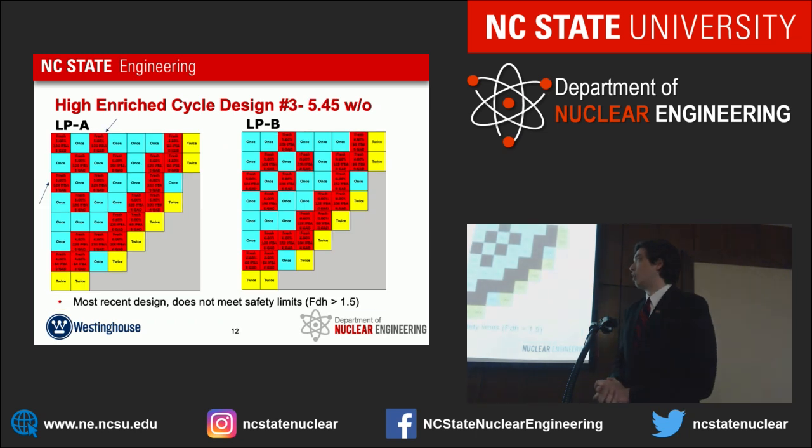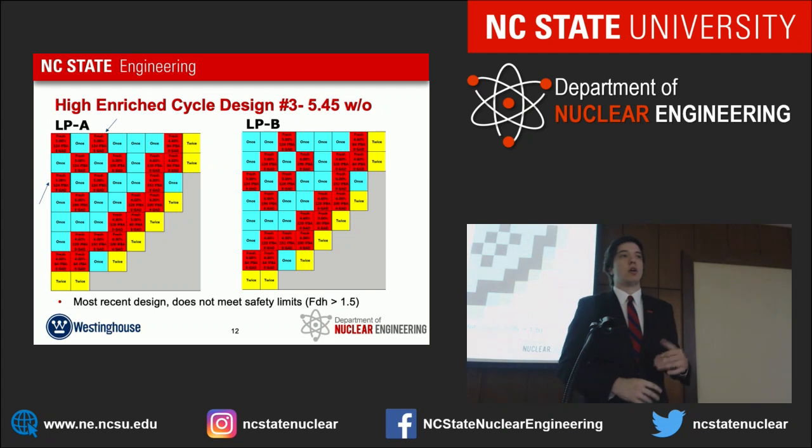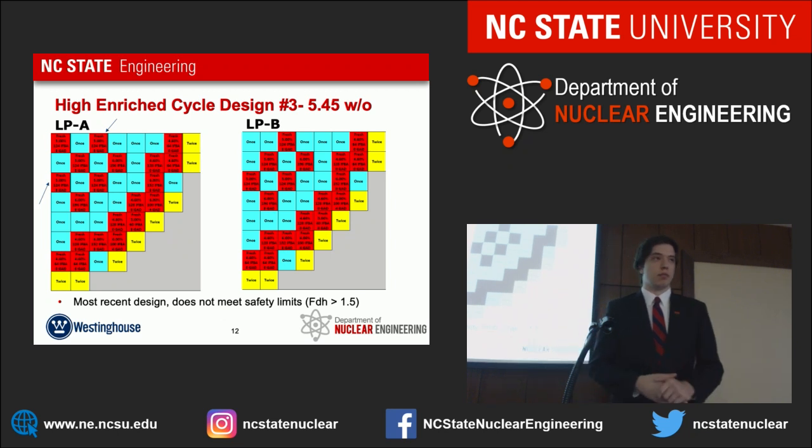And finally, we have our latest test, which sees an increase in enrichment in four assemblies in the core. But unfortunately, we could not get the peaking below 1.5. And so that was the extent of our analysis for our third high-enriched. But all the others met everything and worked well.